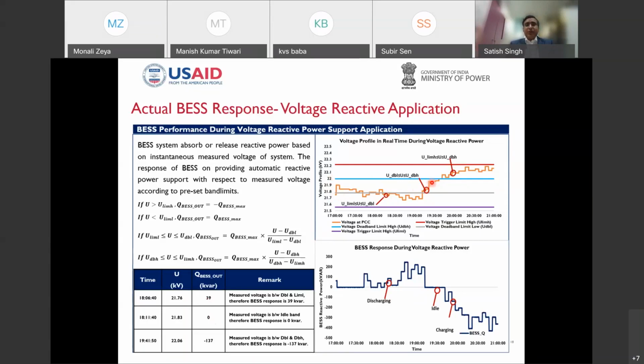But whenever this goes beyond this threshold value, I have a fixed rate, this is a slope of the curve by which it has to generate reactive power. So here, if you say, this is actual voltage observed, whenever this is going below, the battery is discharging. Similarly, these instances, this is becoming idle. So this is second instance. But whenever there is an over voltage kind of condition, the battery is charging and generating reactive power so as to compensate for the over voltage.